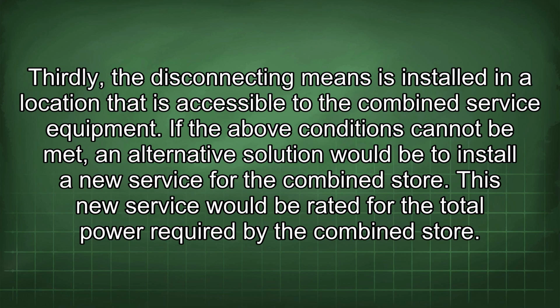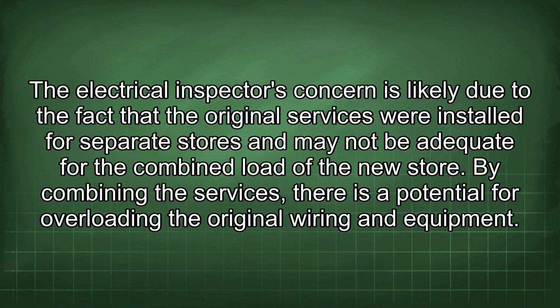If the above conditions cannot be met, an alternative solution would be to install a new service for the combined store. This new service would be rated for the total power required by the combined store. The electrical inspector's concern is likely due to the fact that the original services were installed for separate stores and may not be adequate for the combined load of the new store. By combining the services, there is a potential for overloading the original wiring and equipment.